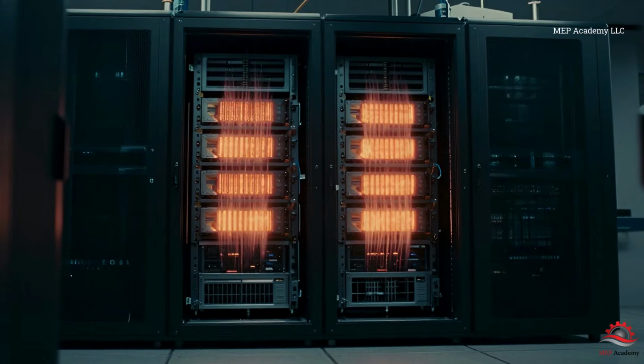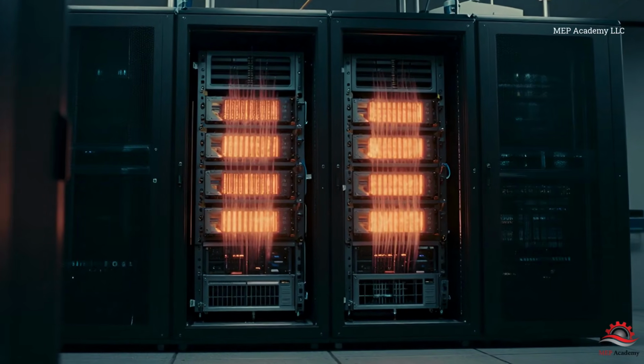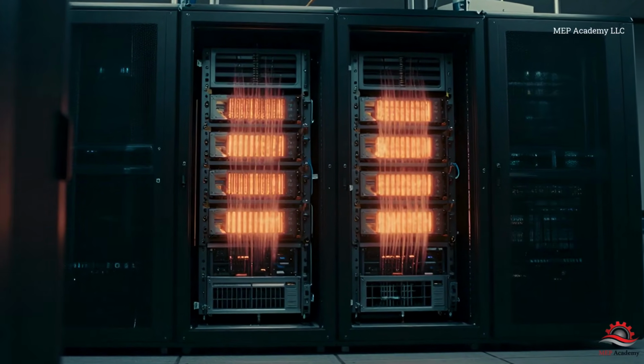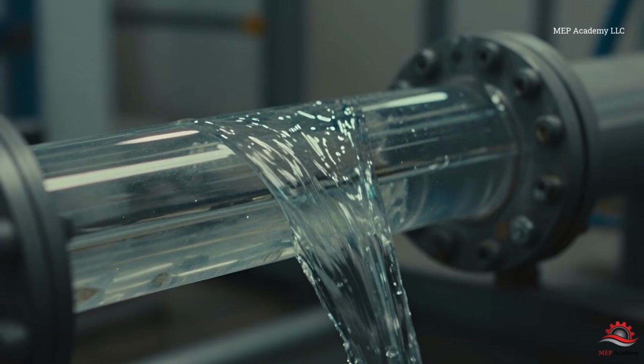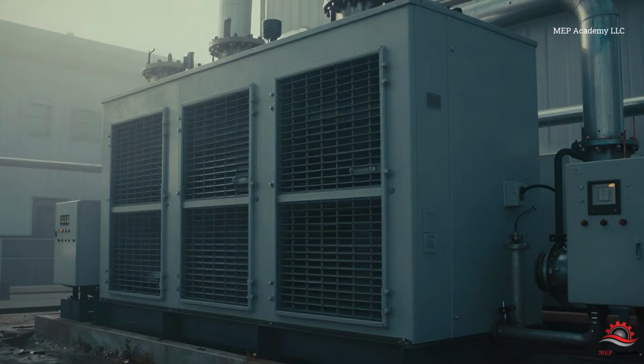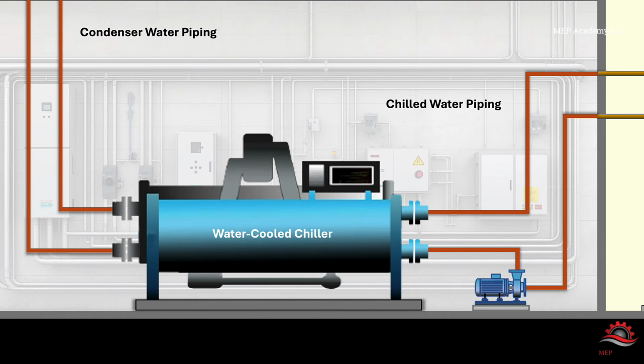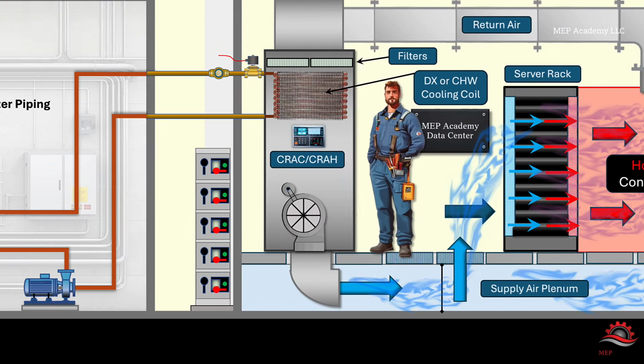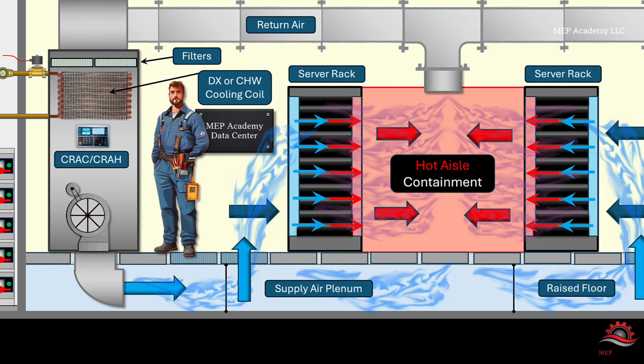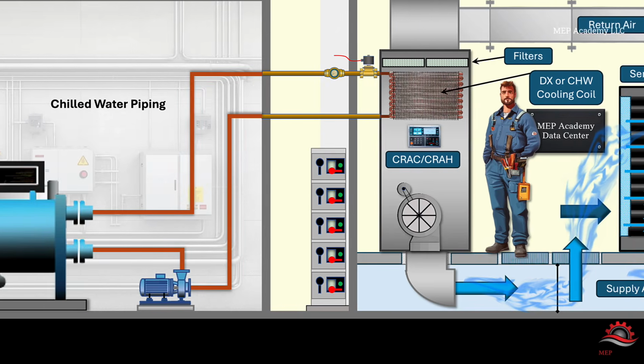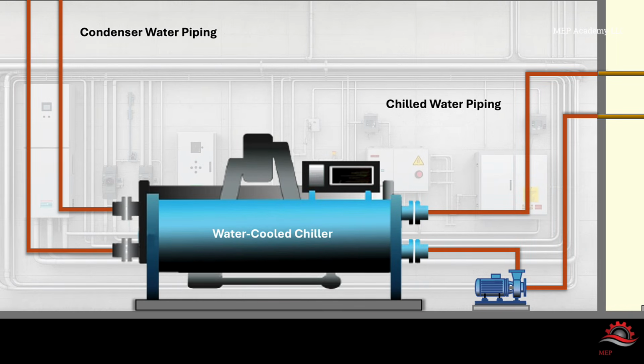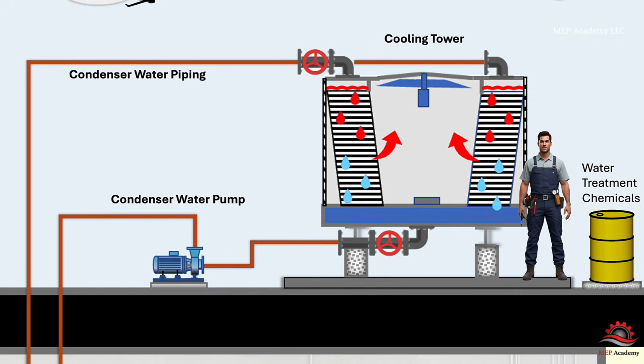What is a chilled water system? At its core, a chilled water system is simply a way to move heat from inside the building to the outside. It does this using water as the transport medium. Here's the basic concept. Cold water is produced by a machine called a chiller. That cold water is pumped through piping into the data center. Inside the data hall, that water flows through cooling coils in units like CRAH systems. Air passes over those coils. Heat transfers into the water, and the cooled air is delivered back to the servers. Then the now warm water returns back to the chiller, where the heat is rejected to the outside environment. And the cycle repeats, continuously.